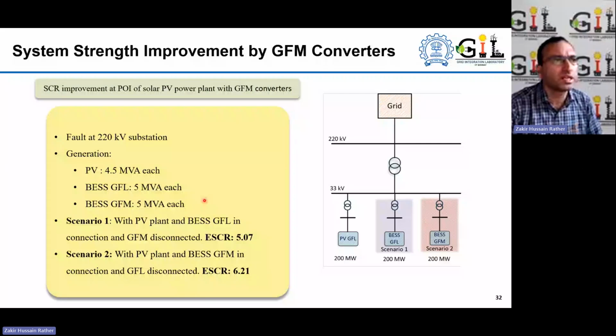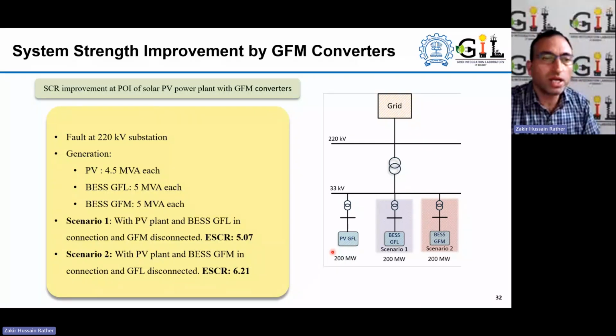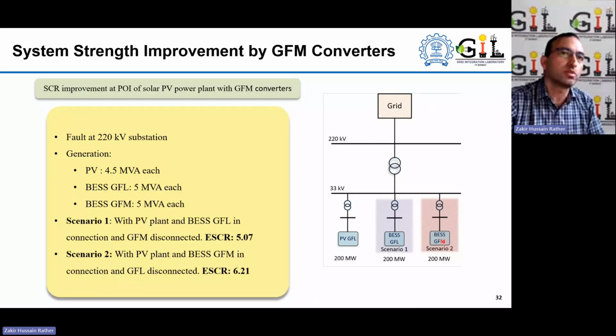We also looked here at IIT Bombay at the impact on the grid strength. This is a simple case study of how grid forming technology can improve the grid strength. In this case, we have a grid following PV power plant of 200 megawatt, and then it's detailed modeling, though here in the single line diagram it is showing aggregate modeling, so aggregate representation. One scenario is a PV plant with a grid following interfacing battery. Another scenario is a PV plant, but with grid forming interfacing of the battery storage.